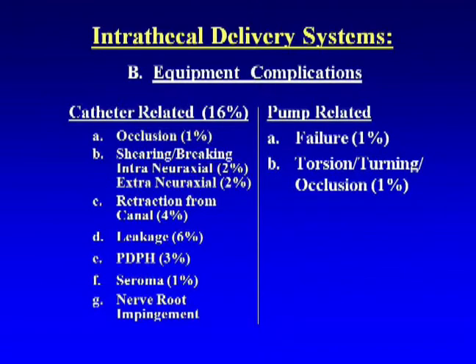Regarding delivery system equipment problems: catheter-related problems occur about 16% of the total complications. These include occlusion, shearing and breaking of the catheter, retraction from the canal, leakage, post-dural puncture headache, development of a seroma, nerve root impingement, pump failure, and torsion and turning of the pump. These are the equipment complications that can occur when using neuroaxial delivery systems.